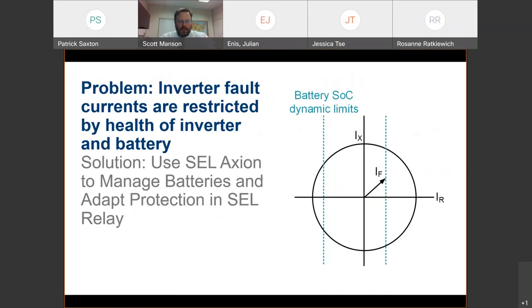All of these phenomena reduce the ability of that battery to produce current. Now, how does that affect the AC side? Well, if you have a fault and it has a significant component of power, meaning there's resistance to that fault, that power has to come from somewhere, and it's coming from your battery. Now, reactive power, some folks analogize this to the foam on your beer, but frankly, it's more accurately described as the out of phase current required to magnetize our world. That's IX, and on a very high voltage system it dominates the fault currents. But on low voltage systems, you very commonly see large amounts of real power being applied to faults. The reason we know this is because inverters are producing it and tripping off on low voltage faults in ways that don't look like a high voltage fault. And in this case, the health of the battery is changing your fault current.